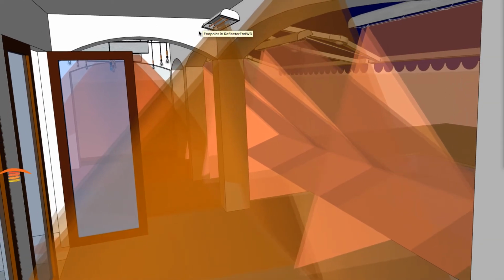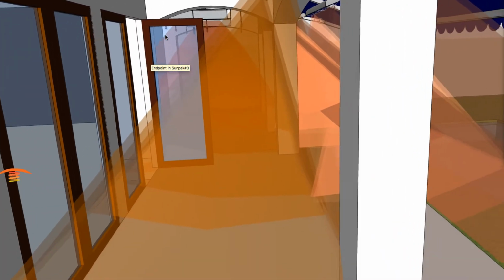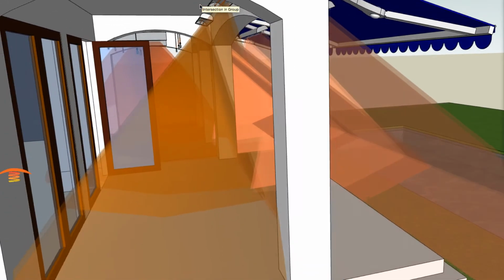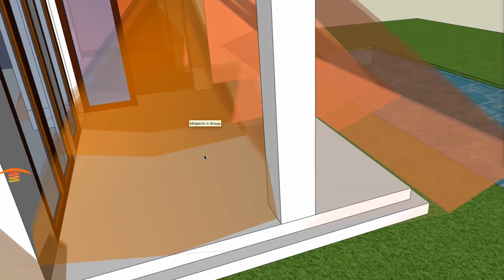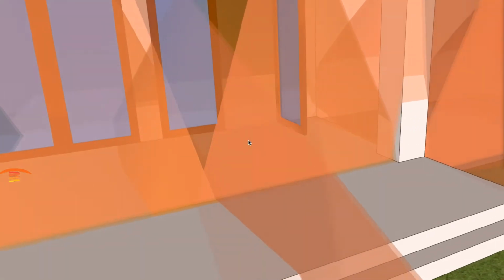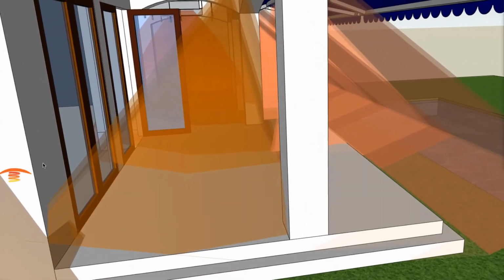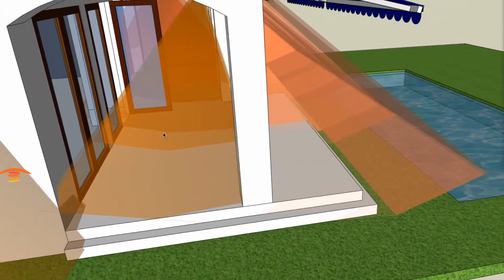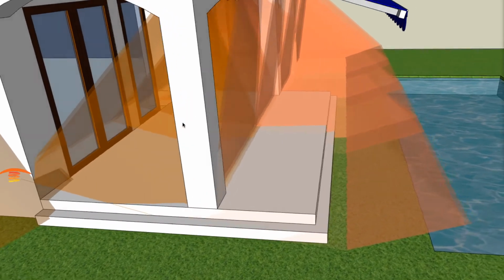And just take a look at what we have here. This is approximate, so that's 52 inches. So that's plenty of distance away from the doorway. And you can see by placing two of these smaller, shorter 5,000 watt unit heaters, you'll have plenty of coverage for this entire space here. You got a nice overlap in the middle, and it goes all the way from the edge to the structure itself. So they'll have a nice comfortable space there, and I think this is one of their number one elements that they want to heat up.